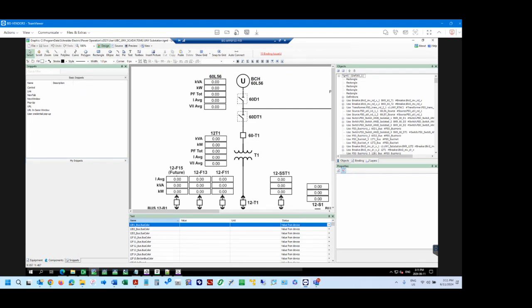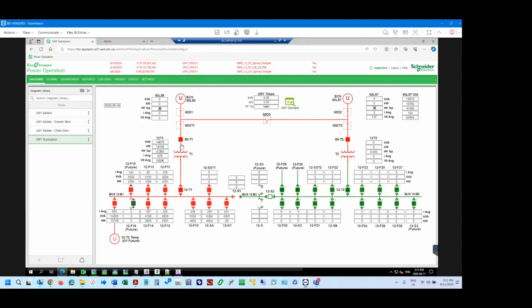Yeah, that sounds similar to what we're talking about. I'm just not sure what you mean by configuration status, because you would capture the states of all the conditions we're passing over, and the real-time values like the load flow values. For example, if we are talking about the status, like open or closed breakers, everything modified here in our model, everything that you see on this single line, would be reflected status-wise. Oh, okay, that sounds good then. Going up to the top, incoming, where you have these switches to the breakers below, and the ties.